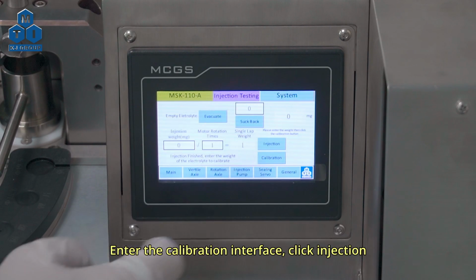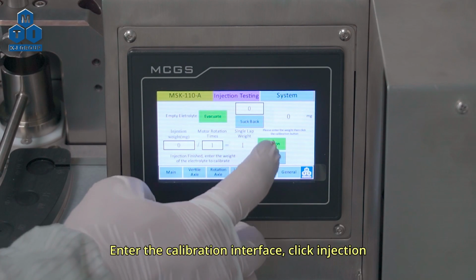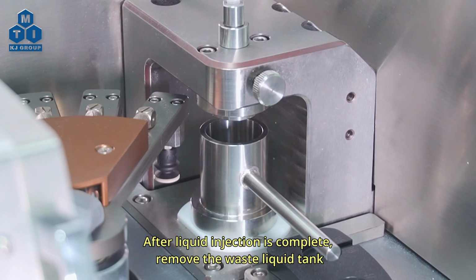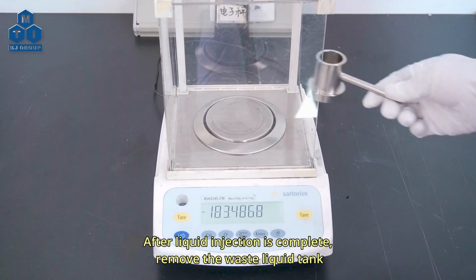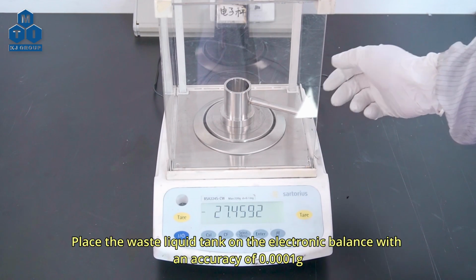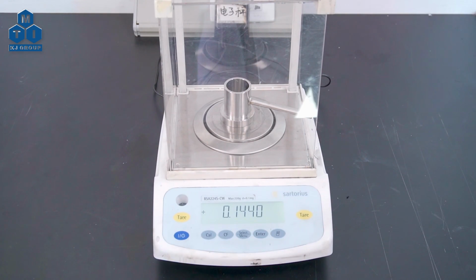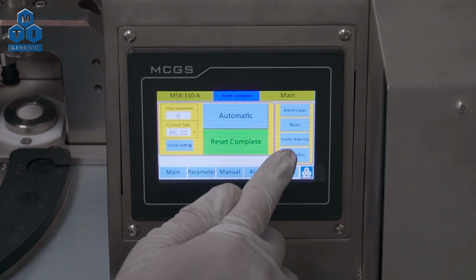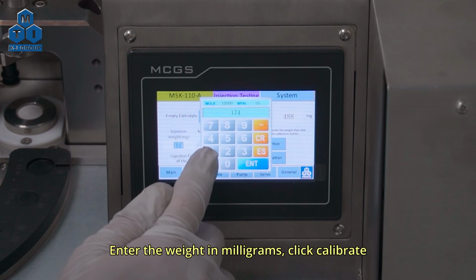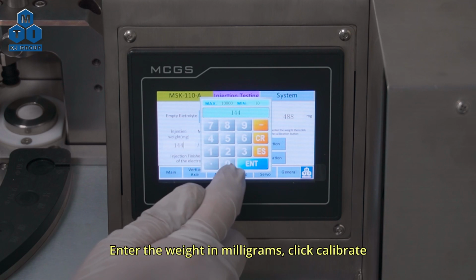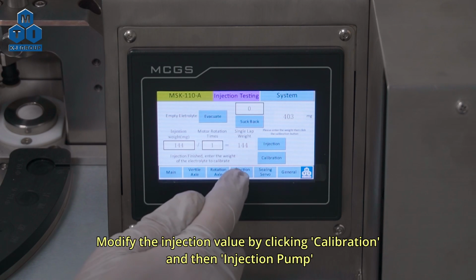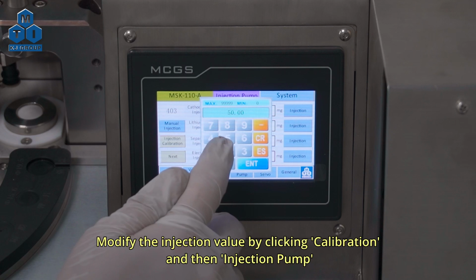Enter the calibration interface, click Injection. After liquid injection is complete, remove the waste liquid tank. Place the waste liquid tank on the electronic balance with an accuracy of 0.0001 G. Enter the weight in milligrams, click Calibrate. Modify the injection value by clicking Calibration and then Injection Pump.